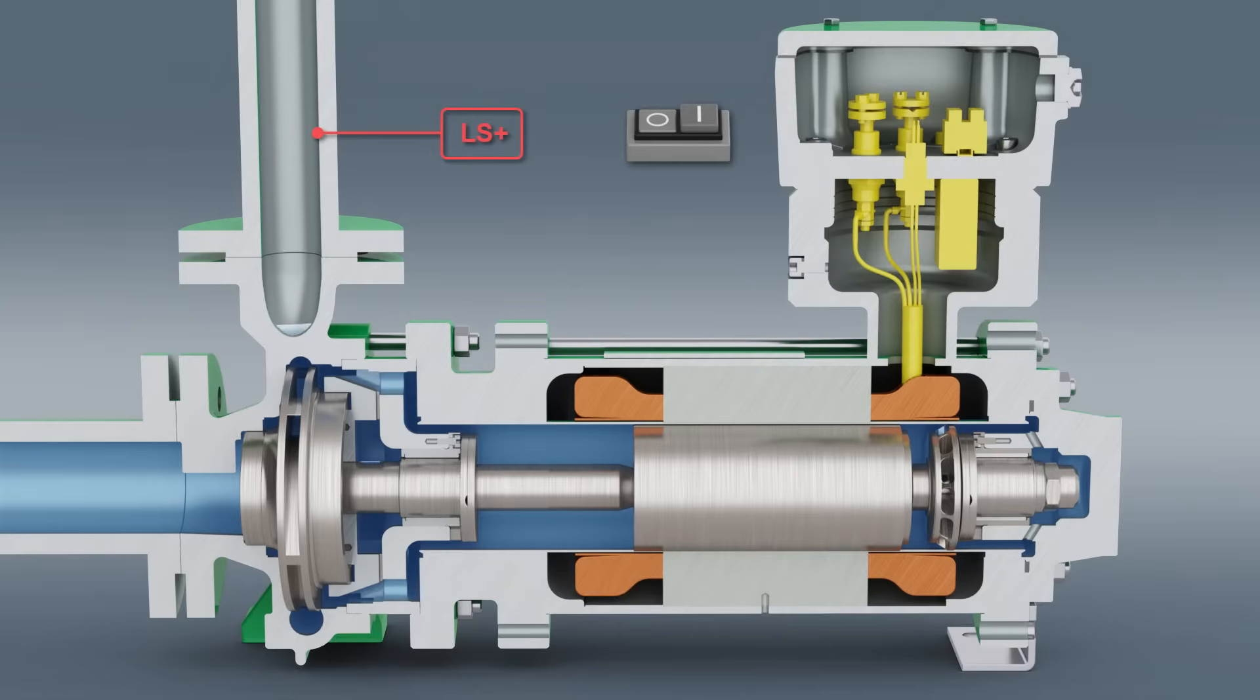During or shortly after filling, potential air pockets at the rear of the motor compartment and in the area of the impeller and bearings are vented out of the pressure nozzle. The hermetic canned motor pump is self-venting.